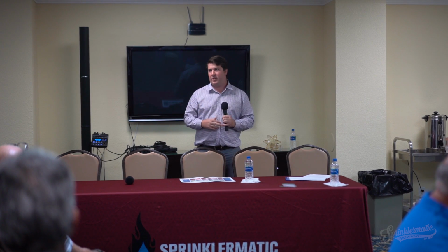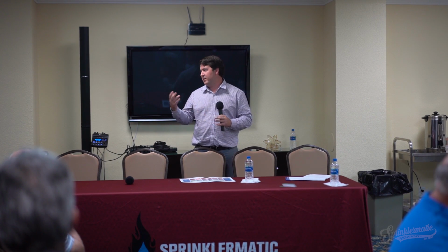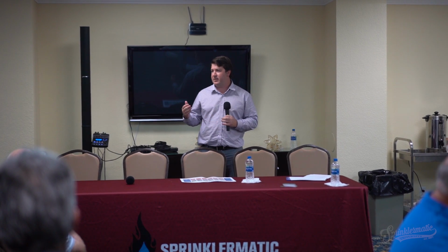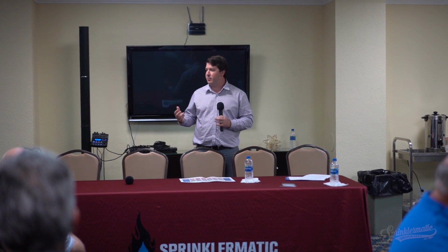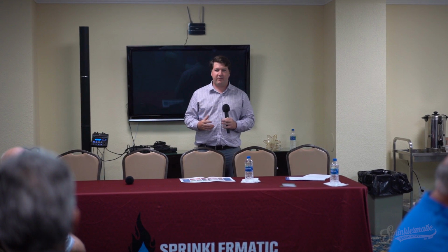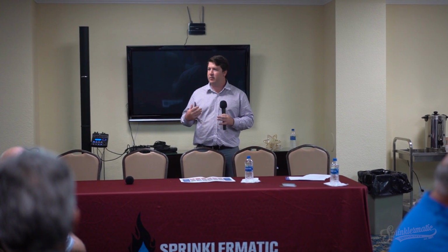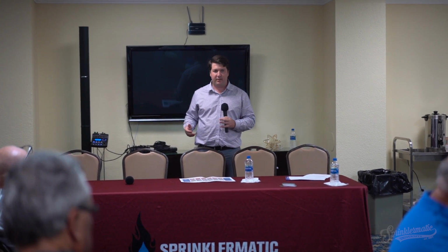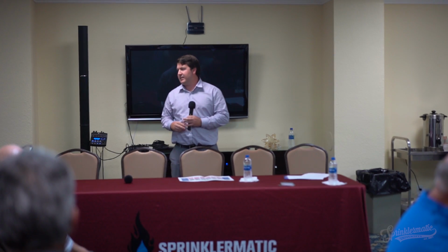So part of that may be expanding your smoke detection to other rooms, such as the assembly room, or bringing them into the units. And it would be one smoke detector as a supervisory basis. The intent is that we're not going to fully sprinkler these units, but you want some type of early detection so we can alert people and get people out of the building faster. In the construction world, that's a scary term.